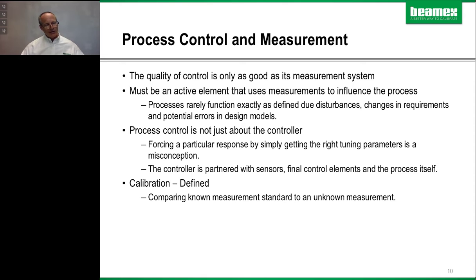So if we look at calibration and define calibration, calibration is real simple. If you Google calibration, just about everything is going to say the same thing. It is comparing a known measurement standard, one that you have a document or a certificate saying, hey, this is accurate, we know it's accurate, and you're comparing it to an unknown. And that unknown is the instrument under test. It's very simple, but can be quite complex at the same time.